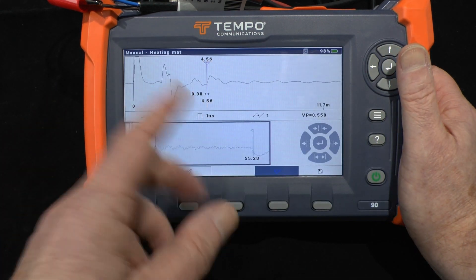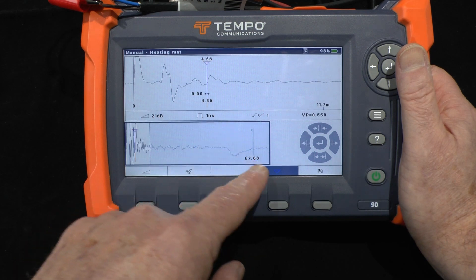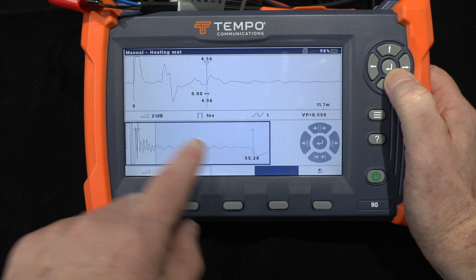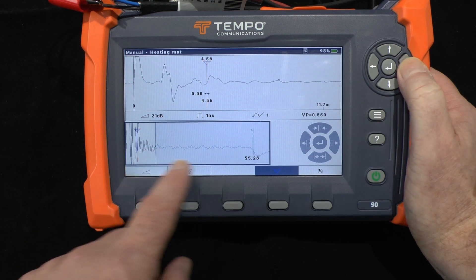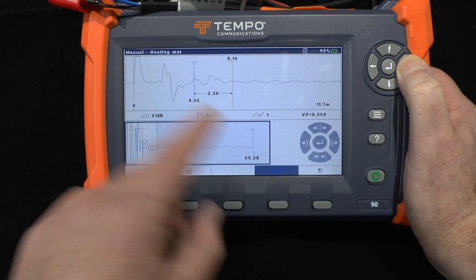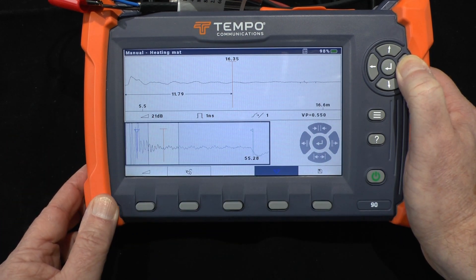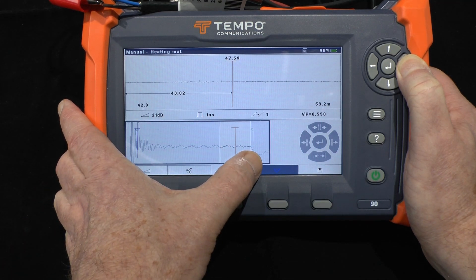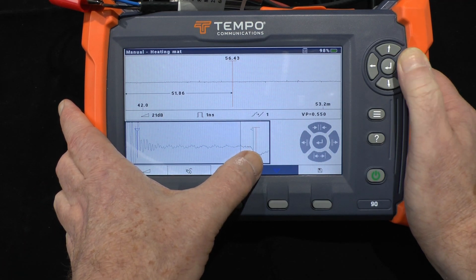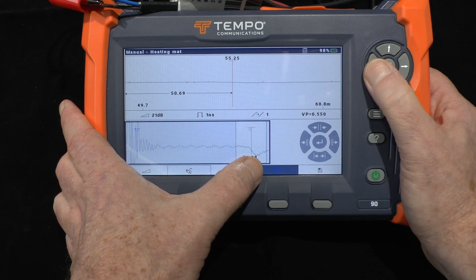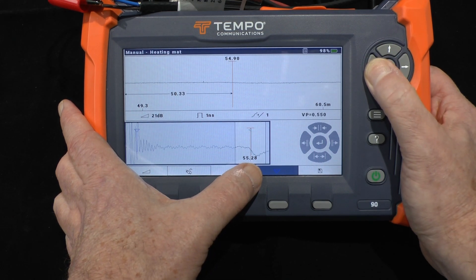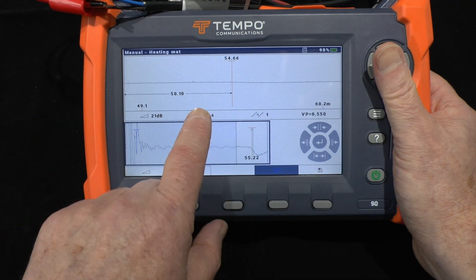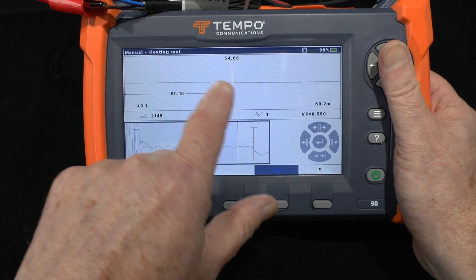With the correct VP we can adjust all the distances. I'll move the window using the cursor keys over to the point of interest. In the lower detail trace we can see what's going on, but there's nothing visible in the upper overview trace. That's because the overview trace uses a 25-nanosecond pulse and the detail trace uses a 1-nanosecond pulse.